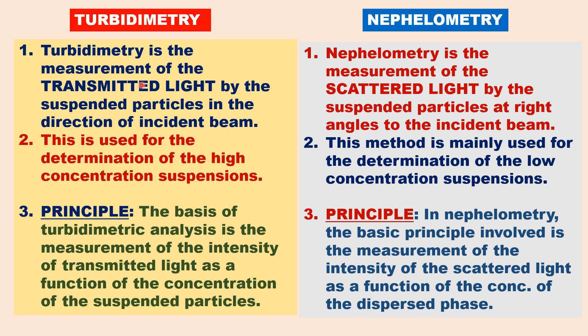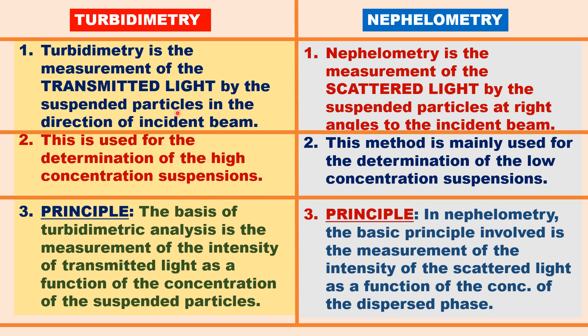Both turbidimetry and nephelometry are related techniques with common instrumentation. The only difference is the detection direction. Turbidimetry is the measurement of transmitted light by suspended particles in the direction of the incident beam, whereas nephelometry is the measurement of scattered light by suspended particles at right angles — perpendicular to the incident beam. Turbidimetry is used for high concentrations of suspensions, whereas nephelometry is used for low concentration suspensions.